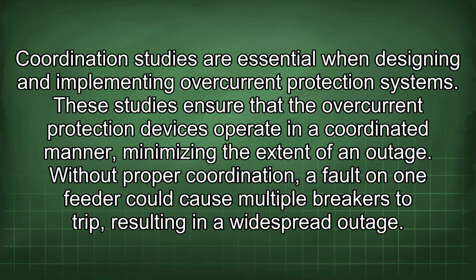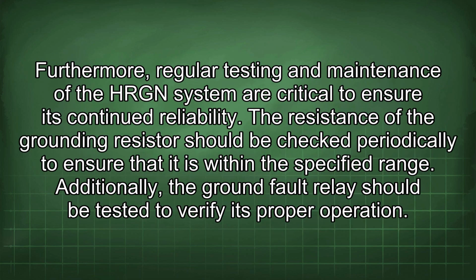Coordination studies are essential when designing and implementing overcurrent protection systems. These studies ensure that the overcurrent protection devices operate in a coordinated manner, minimizing the extent of an outage. Without proper coordination, a fault on one feeder could cause multiple breakers to trip, resulting in a widespread outage. Furthermore, regular testing and maintenance of the HRGN system are critical to ensure its continued reliability. The resistance of the grounding resistor should be checked periodically to ensure that it is within the specified range. Additionally, the ground fault relay should be tested to verify its proper operation.